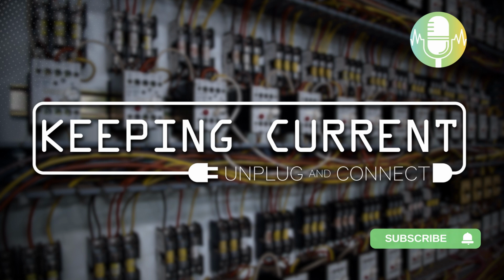Sure, Fred. Something more common today, due to the material shortages that are still very common. More than ever, we are finding significant discrepancies between the equipment ordered based on the design and the actual equipment delivered and installed on site. So not all breakers are created equal. Seemingly subtle differences in breaker and/or trip unit models can lead to significant differences in system performance and therefore arc flash results. For example, the system design may have specified a full function circuit breaker with full LSI protection, but the breakers that are shipped may only have very simple functionality. May not seem like a big deal, but this slight change can have a huge impact on the arc flash calculation results. Accuracy of data for the study is critical.